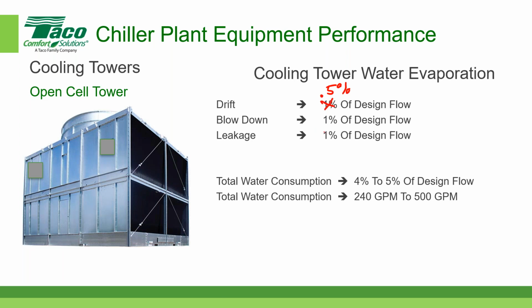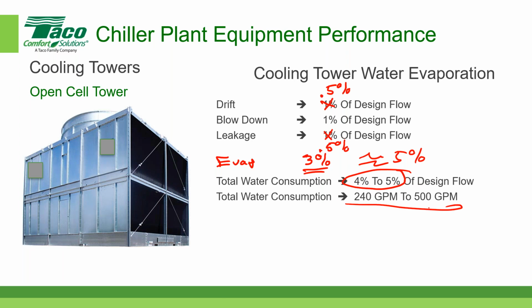This is the blowdown's about 1%. Leakage is about 0.5%. And the evaporation is approximately 3%. So if you add those all up together, that's approximately equal to 5%. So somewhere between 4 to 5% is the amount of water that your cooling tower is going to consume. And in our oversimplified example, that's somewhere between 240 and 500 gallons per minute. That gives you a rough idea of how much water a cooling tower is going to consume based on our system of 2,000 tons.